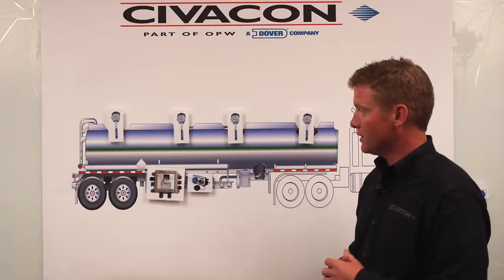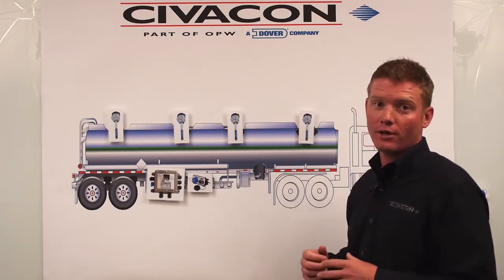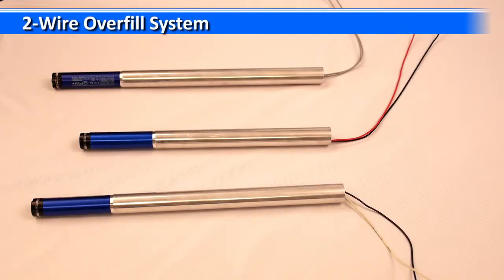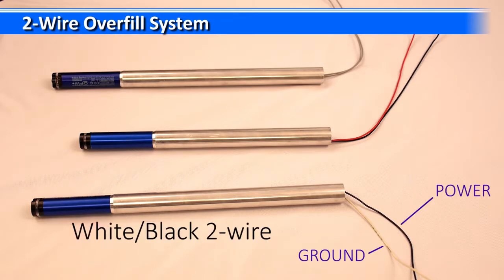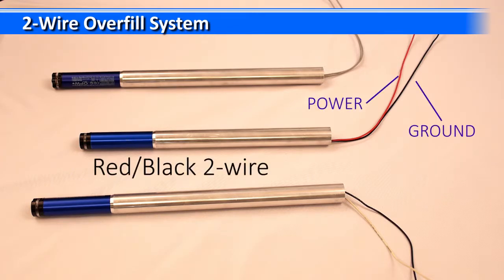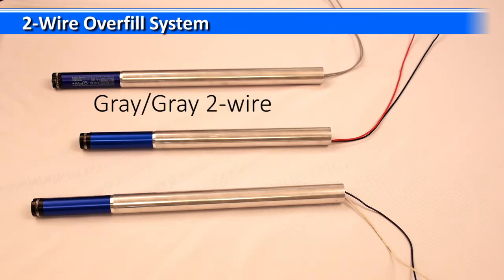And if you have a 2-wire system, then from there we just got to figure out what color wires are your probes. Here are the 3 2-wire overfill probes that you'll see. The first one we have is a white-black with the white being the ground and the black being the power. The red is the power line and the black is the ground line. And the gray probe, it's a universal. The wiring is interchangeable, so it doesn't matter which wire you hook where.